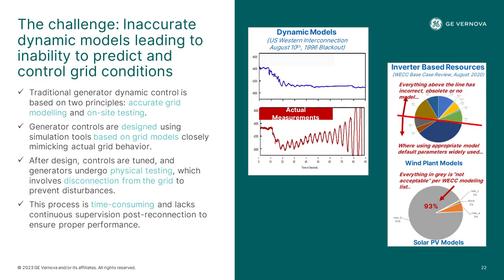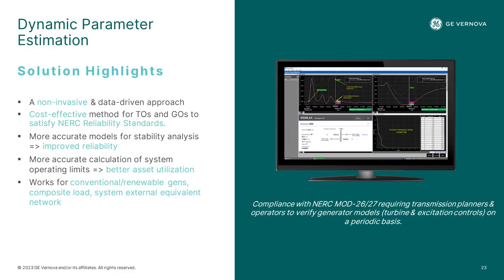The same thing with the solar PV models. What was found was 93% of the PV models were inaccurate. So again, the need for being able to calibrate these models, and this is where WAMS comes in, because as I said, you can observe the dynamics, and it becomes a non-invasive way of calibrating the models, because the conventional way of calibrating models is usually taking the plant offline and running staging tests, which means downtime. Here, using events that have happened on the grid, you can take that data from the events and use it to calibrate the dynamic models. So this is part of our offline application, a non-invasive way of calibrating dynamic models. And I've got a short video here that walks you through the process.